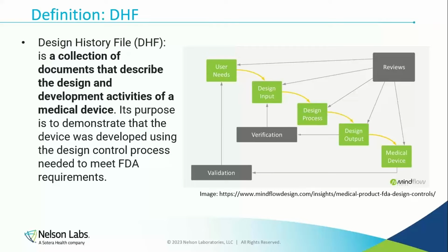And most importantly, you want to ensure that these design controls that you have implemented for your processes, your verification and your validation, definitely meet the FDA requirements, or the country you are planning to file for. That'd be EU, TGA, Japan, China, wherever. There are slightly different variations to these validations from country to country, as we all know, and how you can optimize those variations to ensure that your validation plan is adequate and you have all the acceptance limits specified in your design history file.